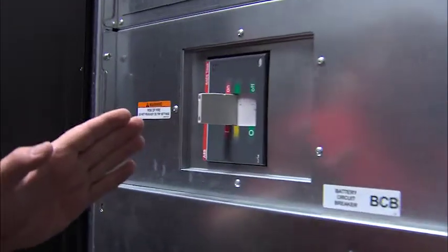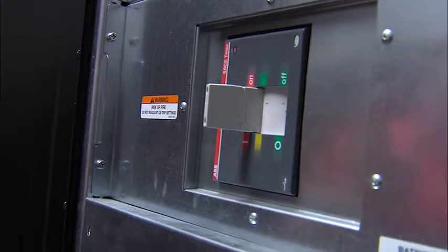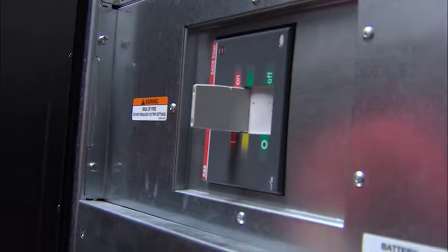So the battery cabinet, let's look at this one so we know it's not as loud. The system has a battery cabinet. It's obviously for arc flash protection. It's double dead fronted, so we can't get in and look at the batteries. If a UPS was to fail, or if you push the EPO button, which I'm going to go over, this breaker will then trip. This breaker will take the availability of DC power or battery backup off of that UPS.